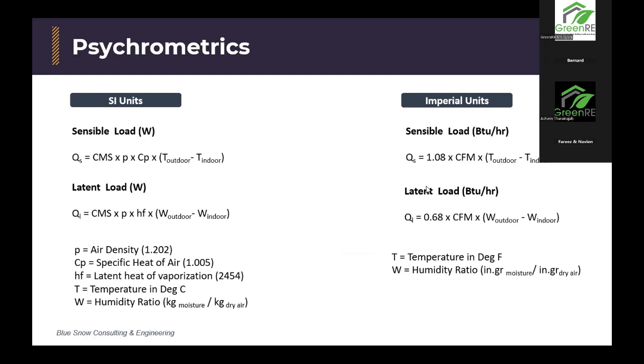Coming to heat load, this detailed calculation is what normally will happen in the last two approaches, and you will be doing it based on the hour, because different hours have different heat exposure from the sun and different times that people come into work. You'll be doing this repeatedly for those detailed calculations, and that's how you'll know your flow profile.